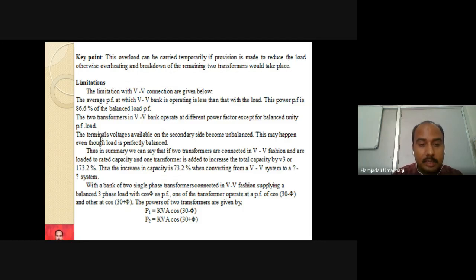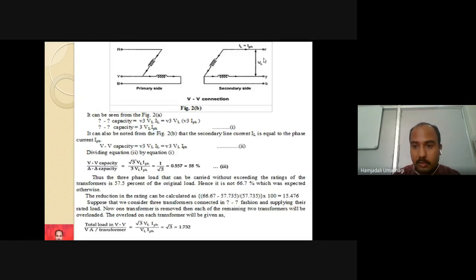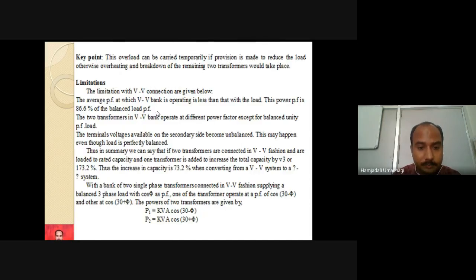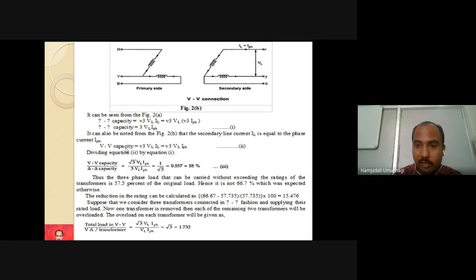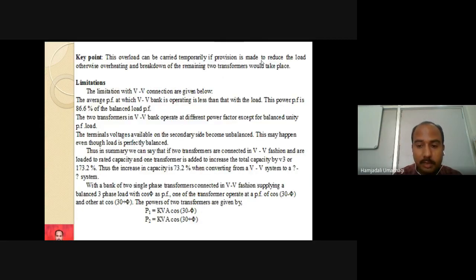Then the terminal voltages available on the secondary side become unbalanced. Here the two voltages are available, you can see here: there is one voltage and this is another voltage. Both these voltages are unbalanced. This may happen even though the load is perfectly balanced. So even if we connect a balanced load on this side, you may still find that an unbalanced loading condition takes place.